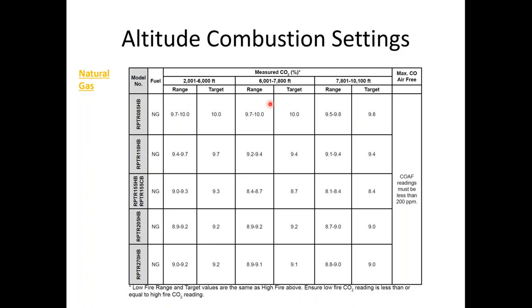One thing I can say, don't chase your tail. If you're setting up a Raptor 85 and we're sitting at like 10.2 here, we're fairly good. Most of our analyzers are going to have a 0.5 plus or minus. Usually start to worry about your CO parts per million. It'll usually fall on natural gas between like the 45 to 90 range when it's in range. 40 to 90 parts per million is around normal for the combustion.